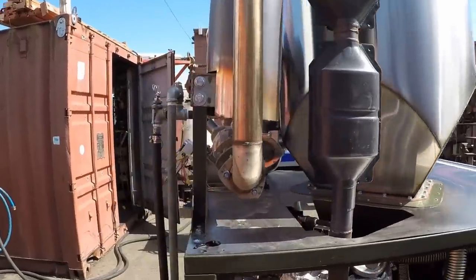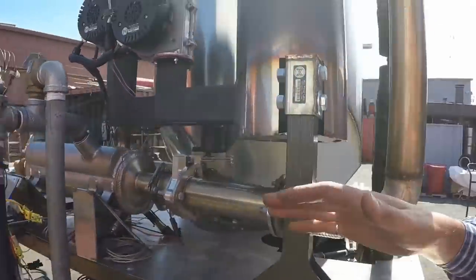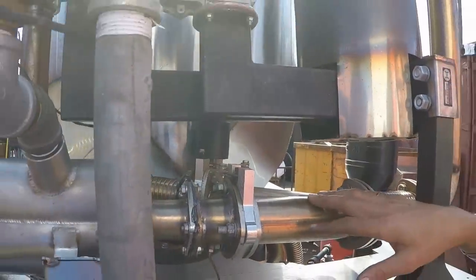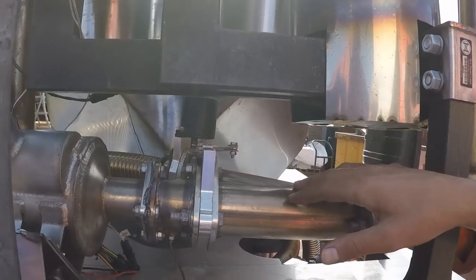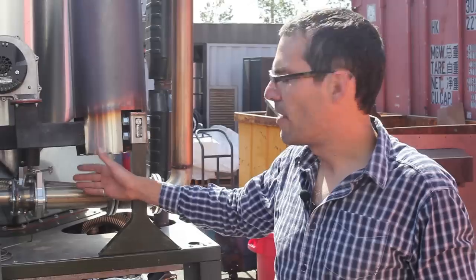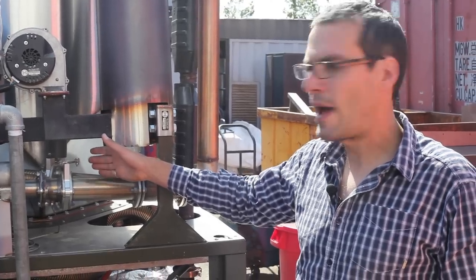And this allows us to safely operate the system with high return temperatures in the working loop. Or if the customers want to use the power cube without the combined heat and power system, then we use this bypass valve to direct the exhaust gas past the heat exchanger rather than through it.